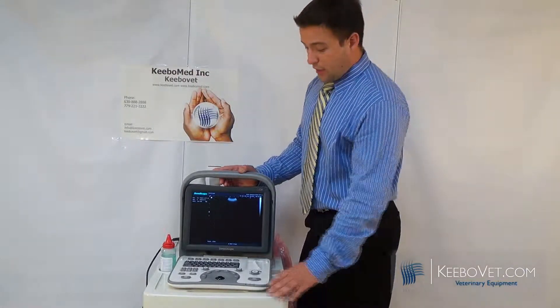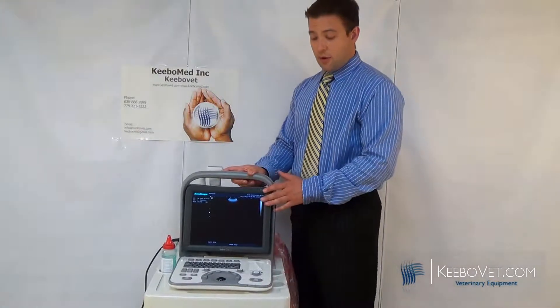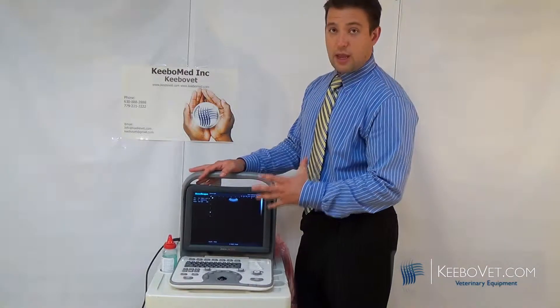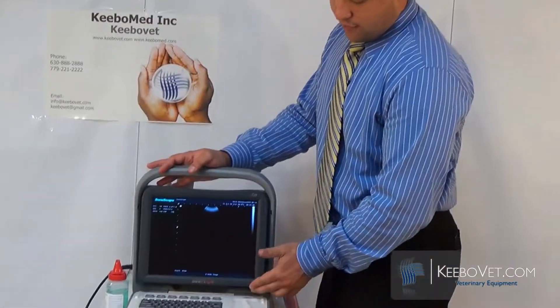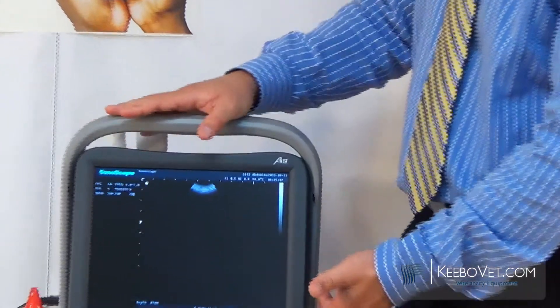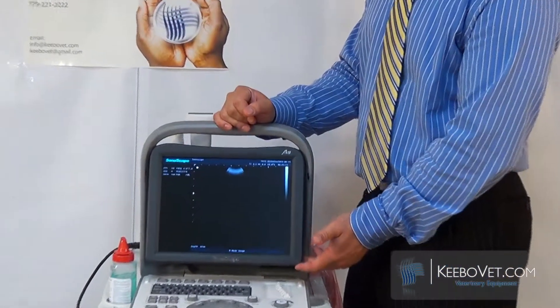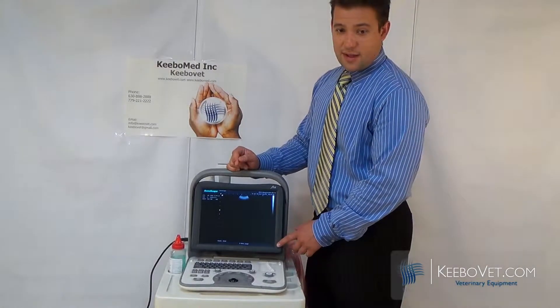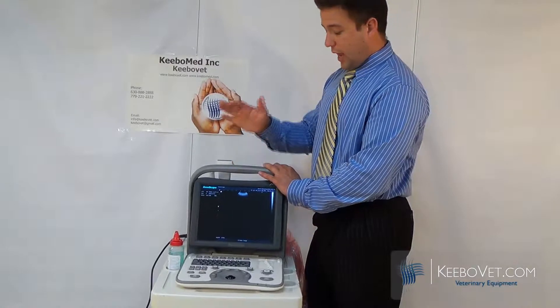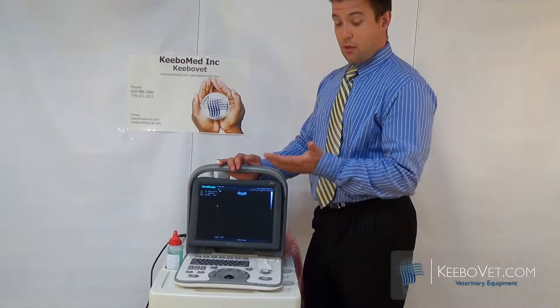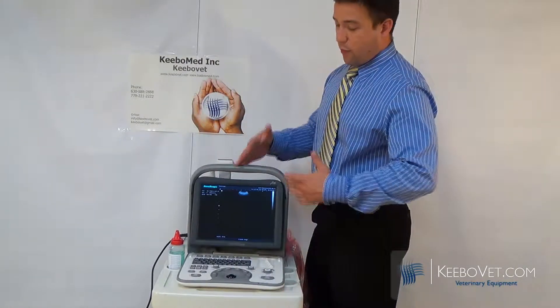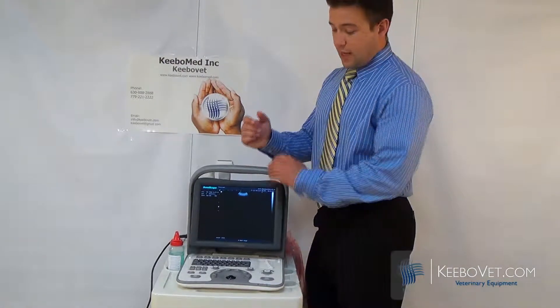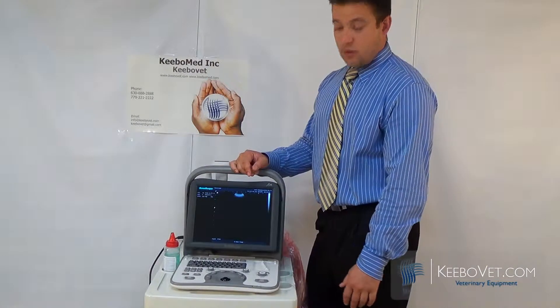For ergonomics, you have a 12-inch screen with a very large image — more than half the screen — so you're not squinting. There's a 30-degree angle tilt on the screen, so if you're taller or in an awkward location you can look more comfortably. You get a three-hour battery, and there are two transducer sockets, so with four transducers available in a stationary location you're more than covered for any setting. The machine is also light, compact, comes with a carrying case, and is overall a great portable system.